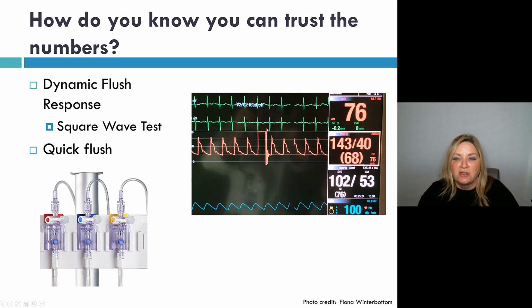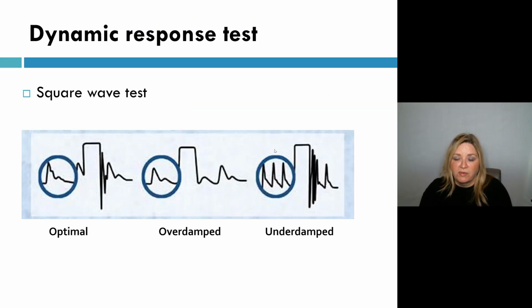You should see a plateau, and then you're going to look for oscillatory waves after that fast flush. If you have 1 to 3 oscillatory waves and they're less than 0.12 seconds from each other, then you can trust that line. That's how we validate whether the numbers are reproducible. So this is what an optimal fast flush test or dynamic response test would look like: a quick squeeze and flush, a plateau, and 1 to 3 oscillatory waves. In an overdamped line, you're not going to have many oscillatory waves, and that's classic. I'll talk about when you see this in just a second. Now, an underdamped line, we will often say the catheter has a whip on it. When you do a fast flush, you see multiple oscillatory waves.